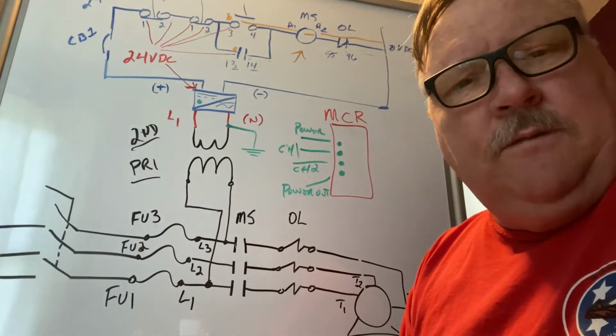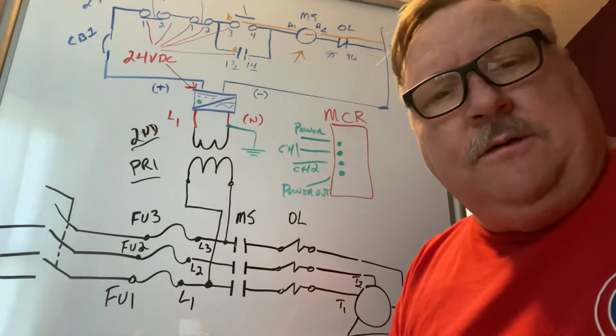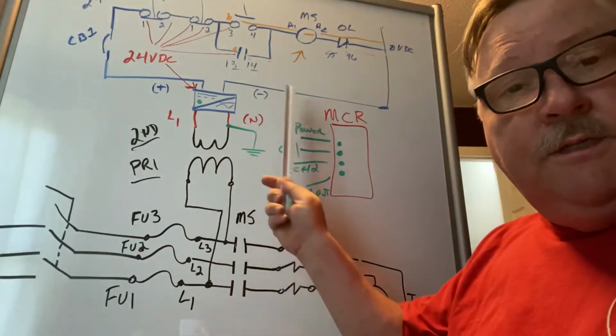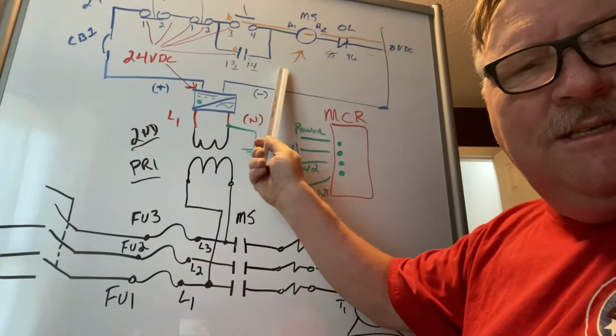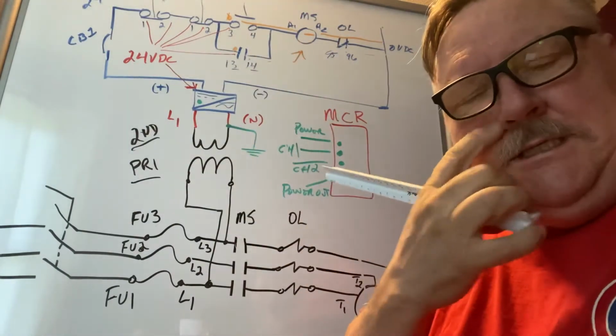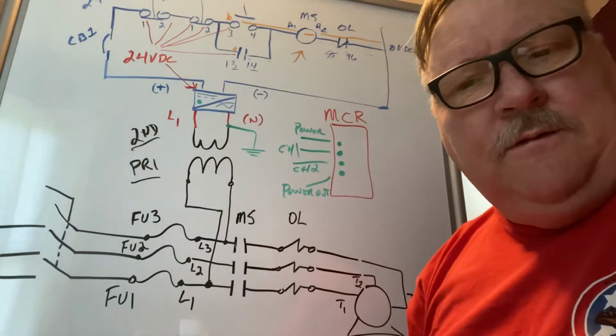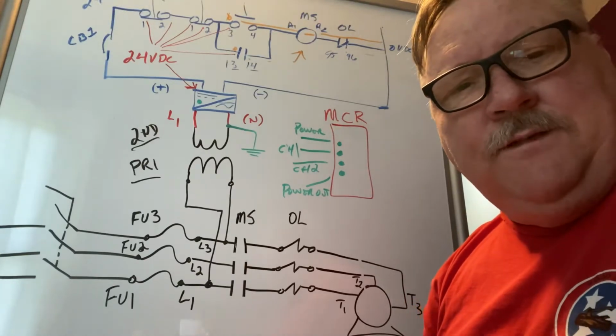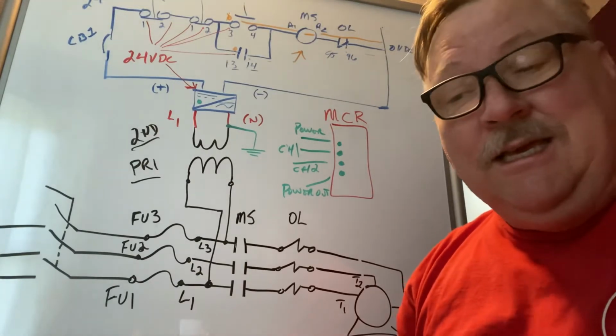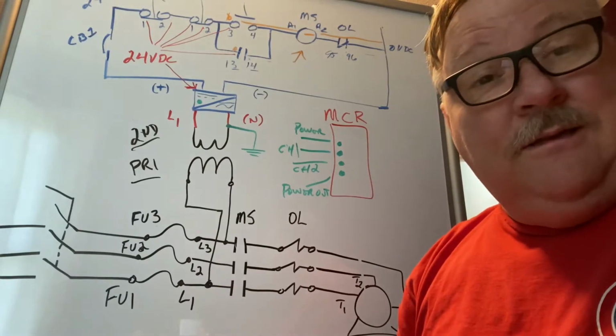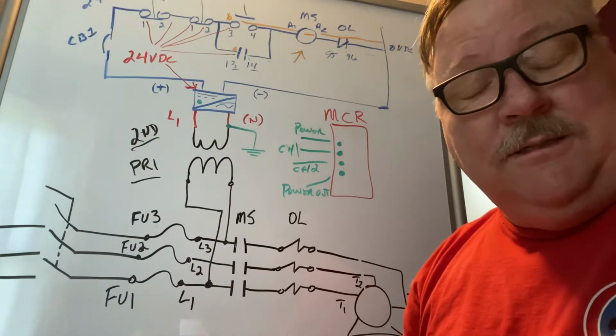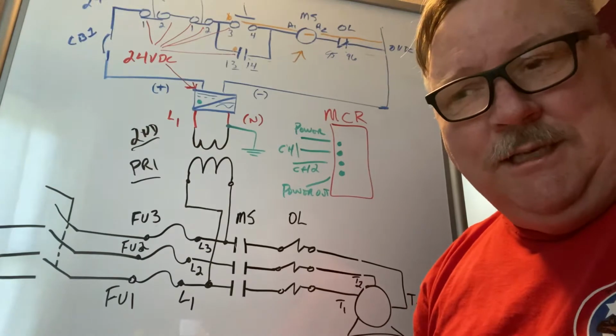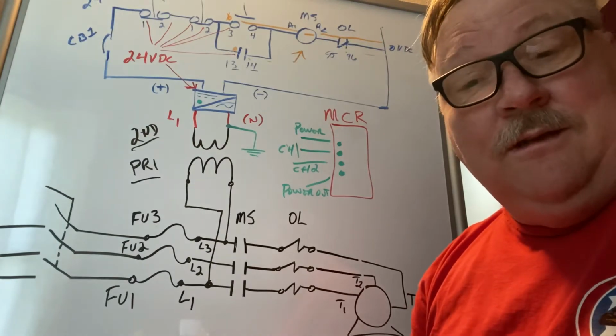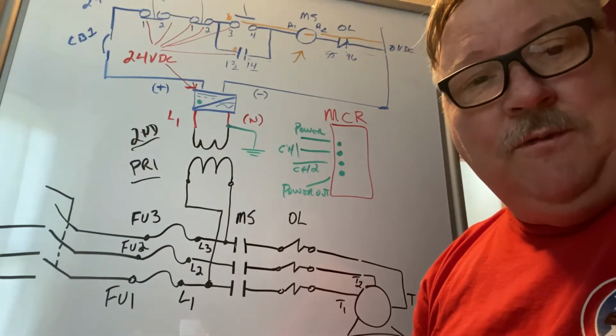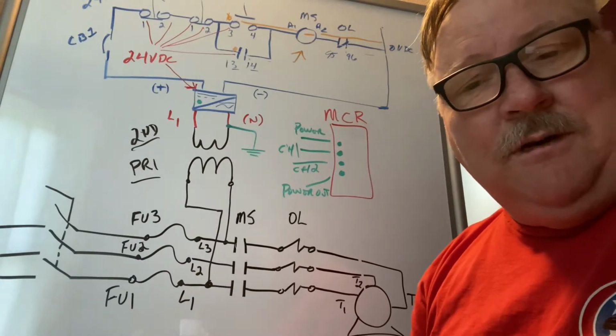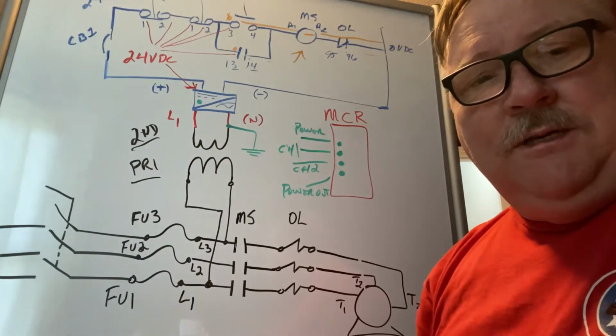The first video that we did was about the control circuit, which is up here. This is the 24 volt DC. They're not always 24 volt DC on the control circuits. Typically, especially if you're in an older manufacturing facility, it'll just be 120 volt AC. Not very forgiving. It will let you know if you're not paying attention that you've touched something live. 24 volt DC is very forgiving. Your PPE requirements with 24 is completely different than what it is when you start messing with 120. So things to be considerate of.